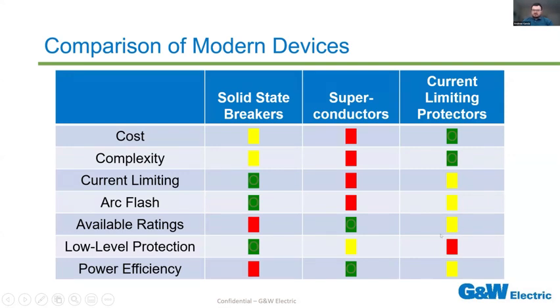Last but not least, you have power efficiency. Superconductors are obviously going to be the best for that. You can't beat near zero electrical resistance. Current limiting protectors are once again just a copper bus bar under normal operation, so that's definitely second place. While solid state breakers do incur a small power loss due to all the electronics that are in there. That needs to be accounted for, but it's not significant, but definitely something that you need to think of when you're using them.